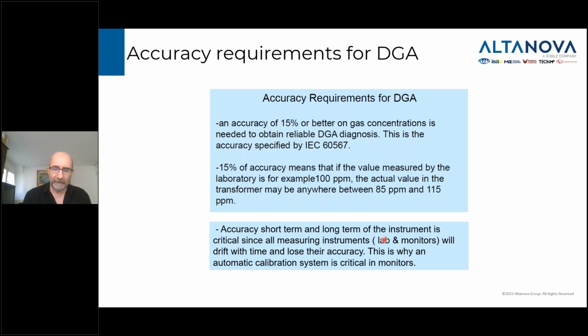Now, you have to look at accuracy short-term and long-term for any kind of instrument. Short-term, because that's when your equipment is brand new, so you know what kind of accuracy the system is going to deliver. And long-term, because as the system ages, the electronics start aging, the detectors start aging, the extraction system gets old, and you start losing accuracy. One way of making sure that your long-term accuracy stays at the same level as your short-term accuracy is to have some kind of calibration system. Either in the lab you calibrate your system manually on a regular basis, or online monitors or portable systems have some kind of regular calibration, so you never lose the accuracy that you had at the beginning when you bought those systems.